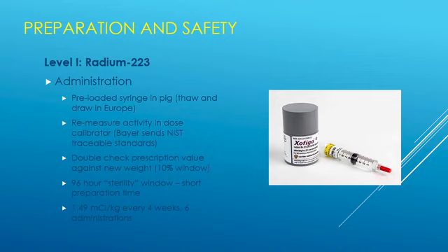The company that distributes this, Bayer, I am going to mention them because, as there is a bit of a dichotomy between nuclear medicine and radiation oncology, there's also that same type of dichotomy between companies that provide drug, in that some are more therapy oriented and some are more diagnostic oriented, that have converted to therapy. And Bayer is a more therapy rigorous type of company. They will send you a NIST traceable standard with instructions on how to calibrate your dose calibrator from the get-go.